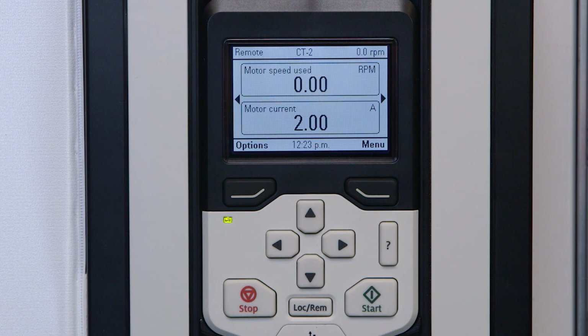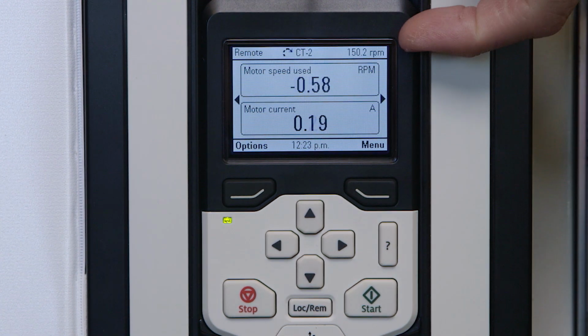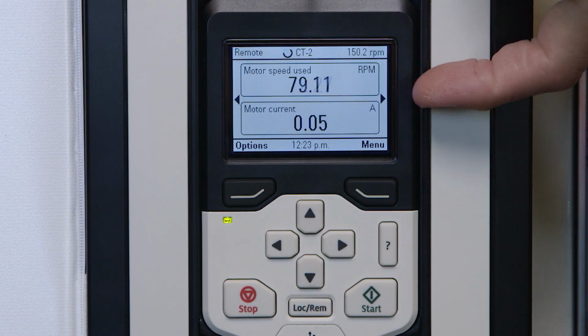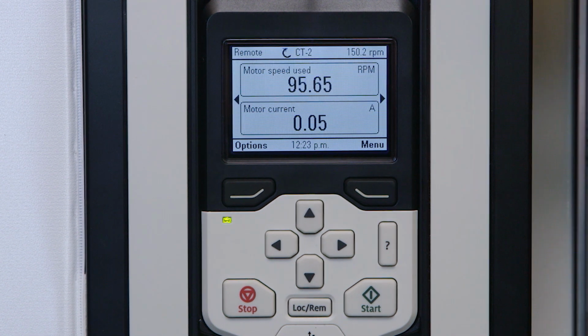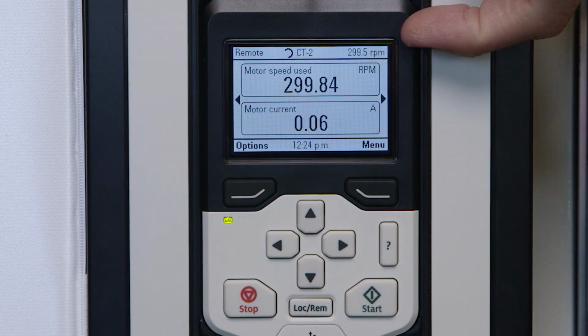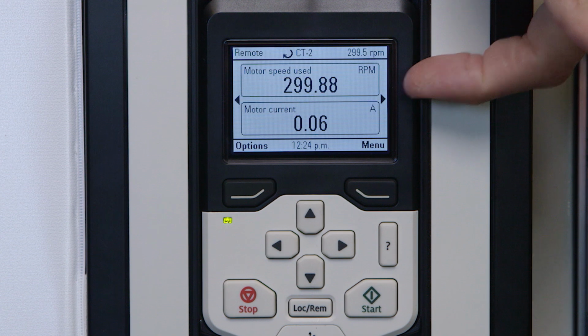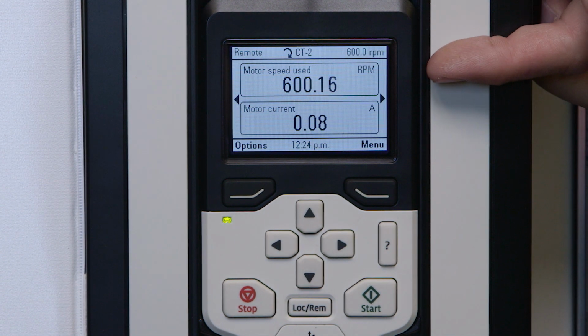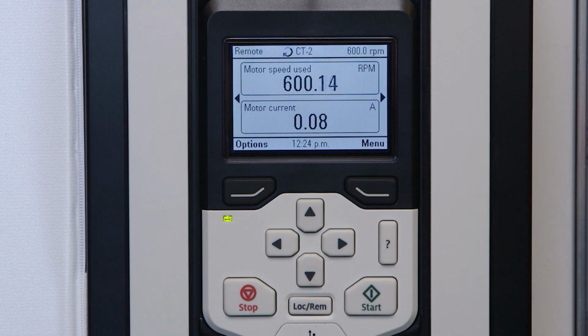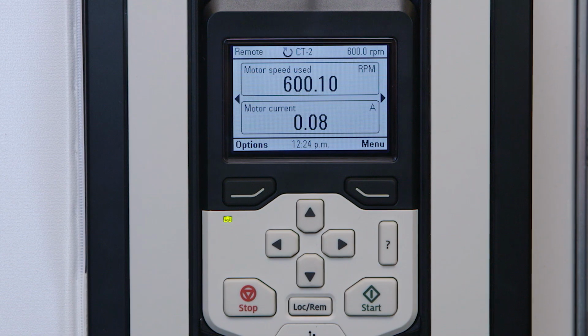Finally, let's confirm that the speed signals are scaling correctly. To do this, have the control send a start command and then a 25% speed signal. Confirm the fan speed is now running at 25%. Next, have the control send a 50% fan speed signal, then a 100% fan speed signal. Confirm that the fan speed is correct for each speed signal sent.